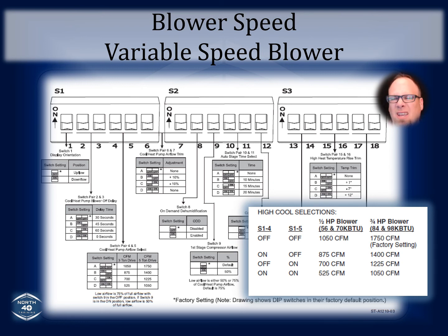But if you had the larger size furnaces, the 84,000 and 98,000 BTU furnaces, then you're going to have the 3/4 horse blower, and that same configuration of dip switches, switch bank 1, dip switches number 4 and 5, will then equal 1,750 CFM. Okay, so you have to make sure that you've got the right blower that you're looking at here as far as your terminal settings and when you set up your dip switches for an ECM motor. Now, it's not rocket science.